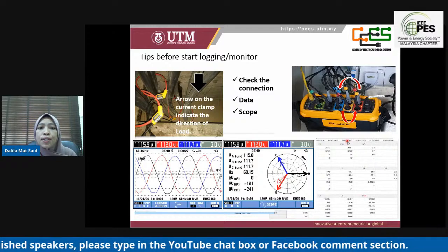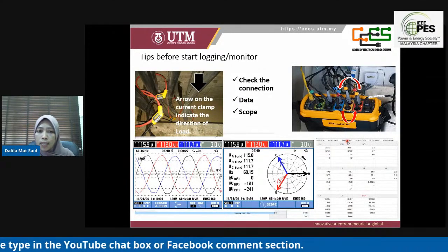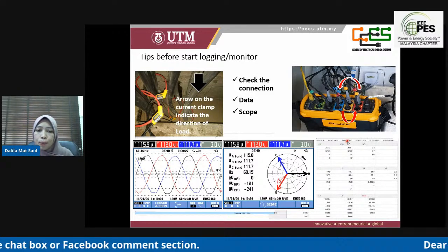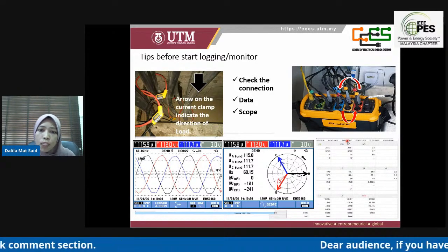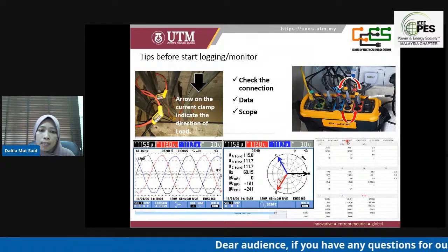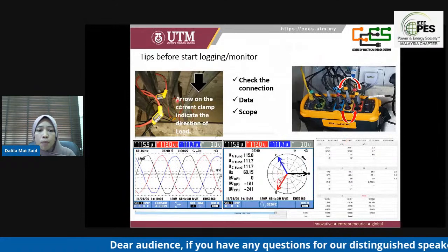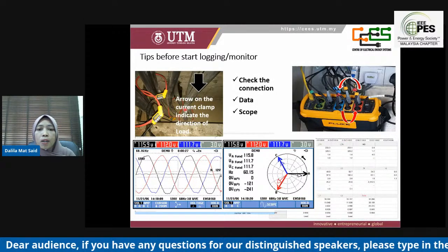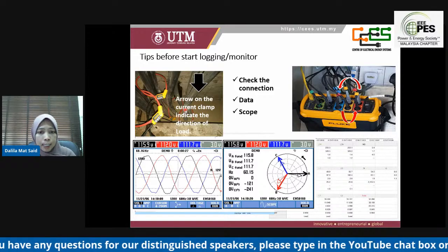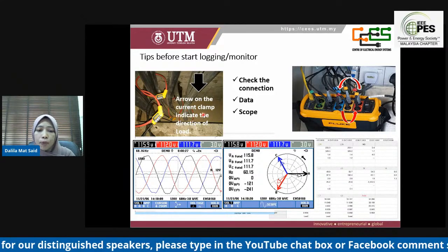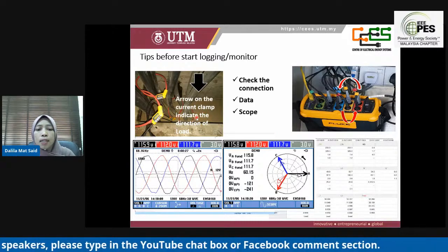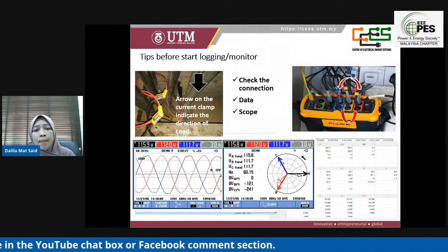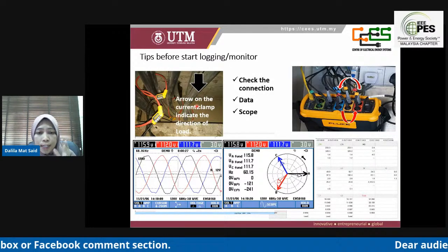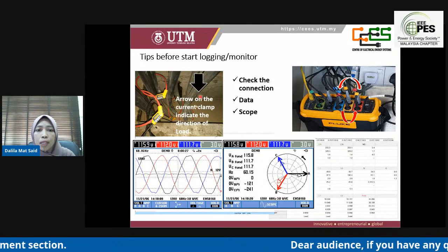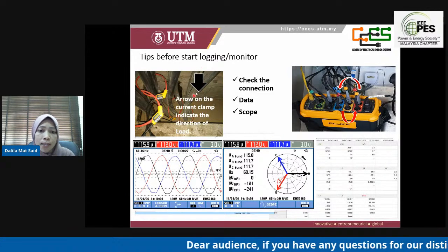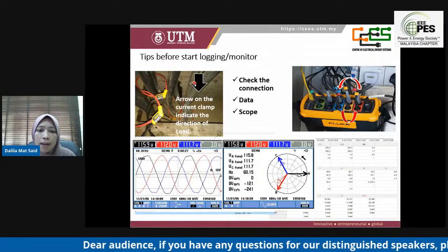So here I will share some tips before we start the logging and monitoring. Of course, in order to handle the measurement or installation, we need to follow the regulation and guidelines. This is a tip before we start the monitoring. Make sure we check all the connections. The tips may also be applied if we use different types of equipment. First, we check the connection at the current clamp. Usually the current clamp provides an arrow that indicates the direction from the source to the load. So we need to carefully check the direction on the current clamp.